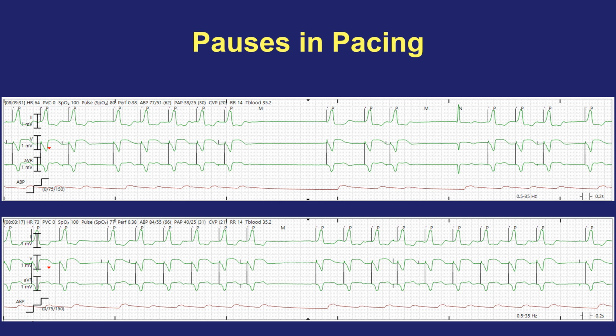The pacemaker box is seeing electrical signals that are not coming from the heart, but of course the pacemaker box can't distinguish one type of electrical signal from another. Electrical signals could also be generated by muscle contractions in the patient's abdomen or chest, by other electrical devices that are near or attached to the patient, or even by movement of the wires themselves. That electrical interference can be detected by the pacemaker box, and it may think that heart activity is occurring and therefore may not need to pace, again called oversensing.